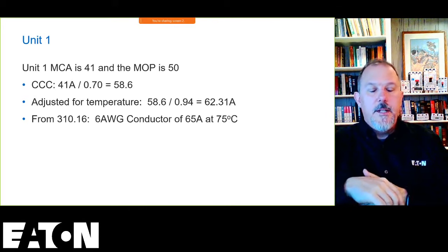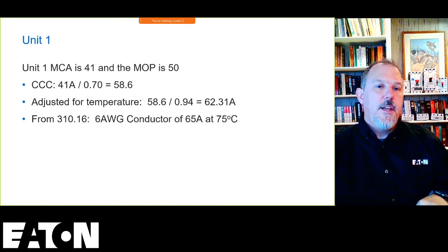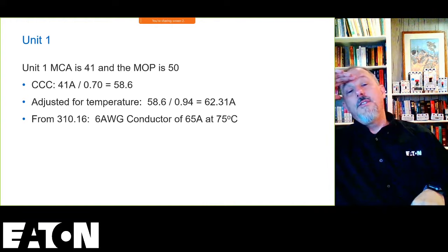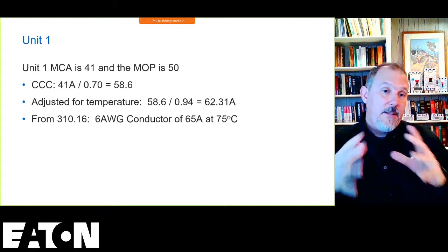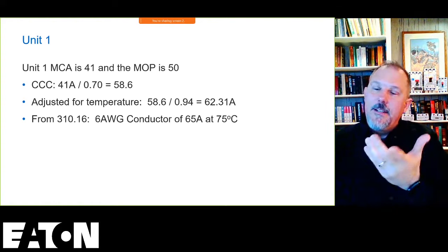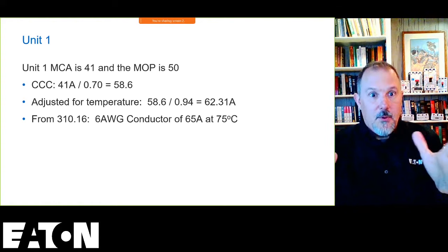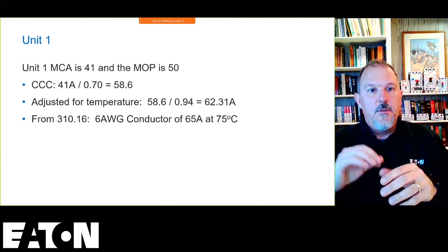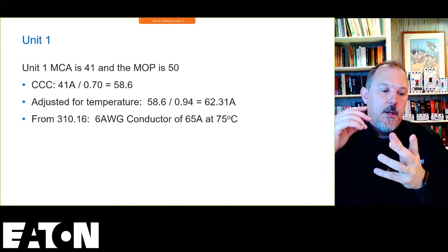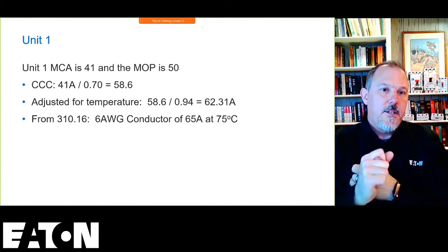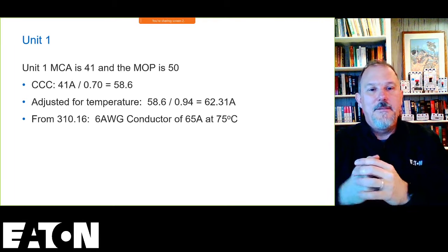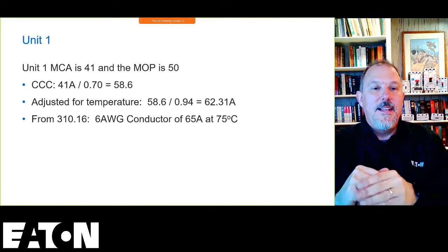For common current carrying conductors, my adjustment factor is 0.7. So again, you can do this one or two different ways. At one point I did this the opposite: I have a spreadsheet, which I didn't show, where I took the entire table and did the multiplying factors so that you can adjust the ampacity of all those conductors based on the current carrying conductor modification and your temperature adjustment. Six of one, half a dozen of another. It's easier just to do this.